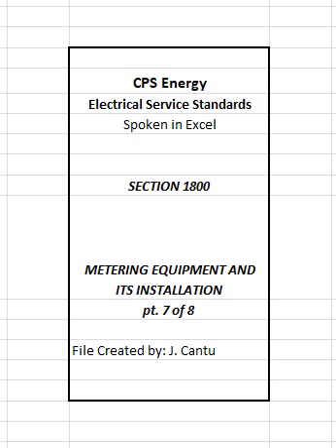of this article. 3. Where a main disconnecting device is installed in accordance with the NEC, it shall be prominently marked to identify its function. The words main disconnect shall be prominently displayed, refer to figures 1814 through 1816.